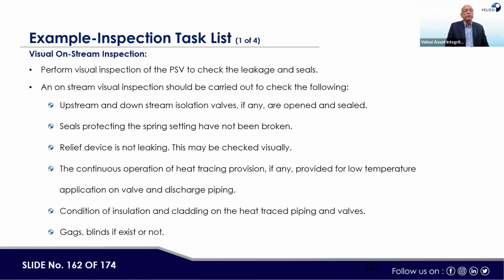And then this is the PMR, like what activities are to be done for this PSV on a 2 monthly basis and a 36 monthly basis. Now visual on-stream inspection: normally, we perform visual inspection of PSVs to check the leakage and seals. The on-stream visual inspection should be carried out to check the following: upstream and downstream isolation valves, if any, are opened and sealed, seal protecting the spring setting has not been broken, and the relief device is not leaking. This may be checked visually.